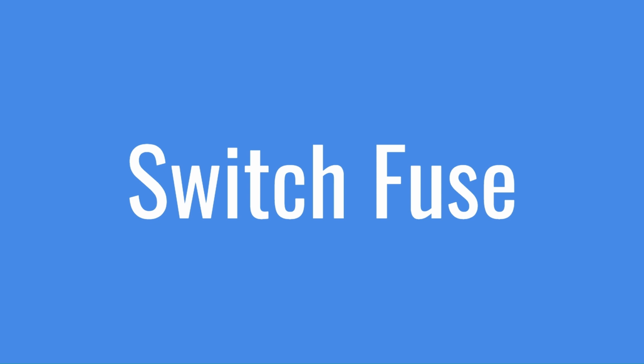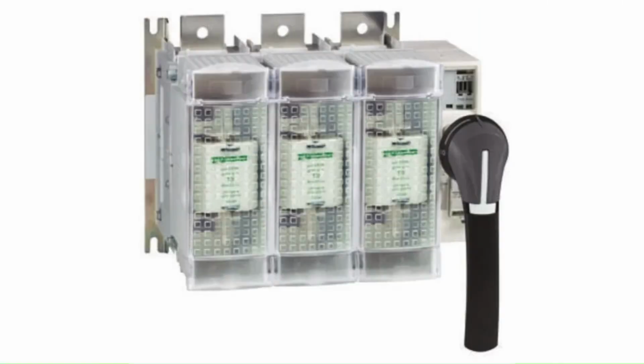Switch fuse is used for low and medium voltage circuits. The rating of the fuse unit is in the range of 30, 60, 100, 200, 400, 600, and 800 amperes. The fuse unit is available as a 3-pole and 4-pole unit. The making capacity of such type of fuses is up to 46 kiloampere. They can safely break current of the order of 3 times the load current.